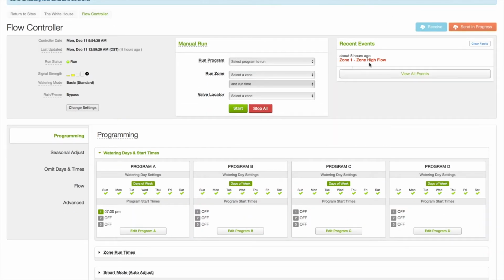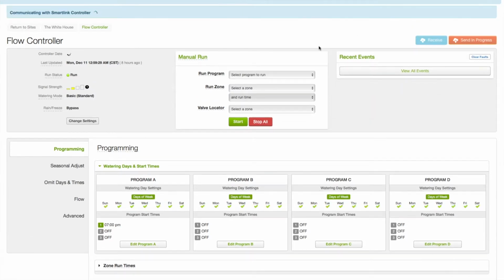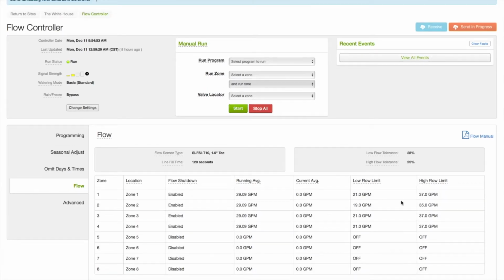Okay, so I have this fault remaining. If I clear this fault, it will actually remain in the error card. That flow fault does not go away until I have a good run. In other words, this zone will have to run in between these thresholds in order to clear that alert. Just clearing it here does not clear it in the software.